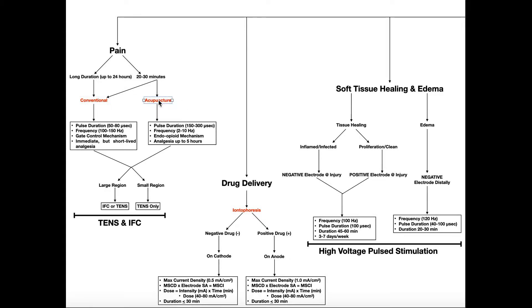Choosing between conventional and acupuncture settings really depends on how long you want the pain reduction or analgesia to persist after the treatment. The acupuncture setting on TENS and IFC will allow analgesia up to five hours after the treatment is complete. So if you want somebody to be able to walk out of the clinic and have analgesia for at least a couple hours after they complete that treatment, then the acupuncture treatment is going to be the best option, assuming they can tolerate it. For that, the pulse duration is set between 150 and 300 microseconds, and the frequency is set between 2 and 10 hertz.